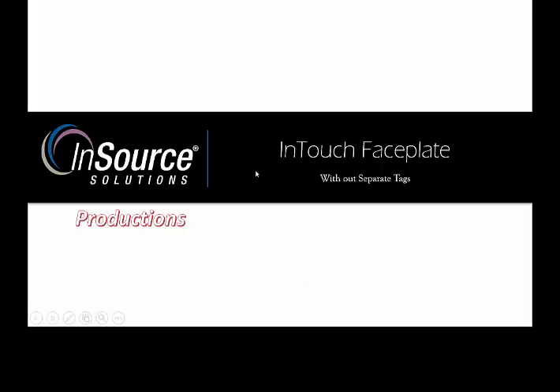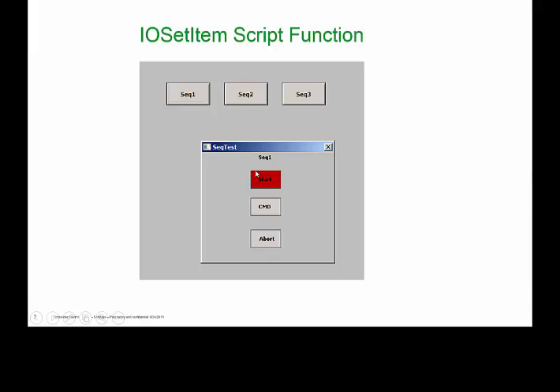So basically the customer called me and said hey I want to be able to pop up a faceplate from one of these push buttons here and then give the ability to send a command down to the PLC or read some status from the PLC but it's just faceplate information, information that does not need to be in tags, there's no alarming, there's no trending. So we can do some things where we just use a standard set of tags, a handful of tags, and change the pointers to the IO address in the PLC to reuse the faceplate and use the same tags over and over again without having to recreate those each time.